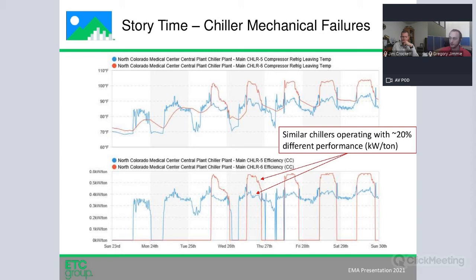It could be things like low refrigerant, like Jim had expressed. You can see that in your approach temperatures. You can have too much refrigerant. You can have flow concerns or flow issues where you're overflowing or underflowing the system. That'll impact the ability of the heat transfer to get out of the refrigerant or into the refrigerant, depending on how you want to look at it. If you have maybe too much oil in the system, maybe overfilled the oil or put it in twice, I know that sounds crazy, but I've seen it. That'll actually impact the heat transfer as well.